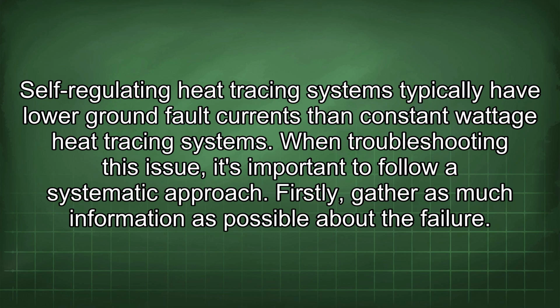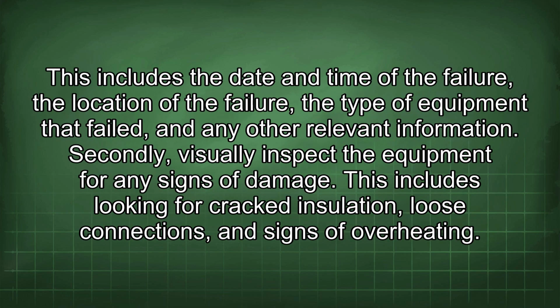When troubleshooting this issue, it's important to follow a systematic approach. Firstly, gather as much information as possible about the failure. This includes the date and time of the failure, the location of the failure, the type of equipment that failed, and any other relevant information. Secondly, visually inspect the equipment for any signs of damage. This includes looking for cracked insulation, loose connections, and signs of overheating.